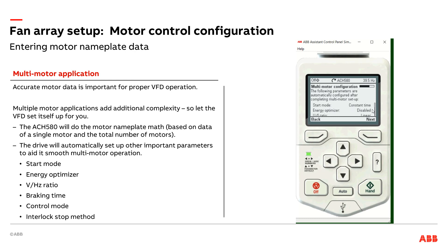Energy optimizer has been disabled. One of the neat things with the drive is it can vary the voltage based on frequency — normally that's how it controls speed — but it can also adjust that voltage at a specific frequency to find the sweet spot for energy efficiency. That works well with a single motor application. With a multi-motor application it just doesn't work as well because you increase the chance of getting a bad spot where you might stall out. So by default we disable the energy optimizer functionality to avoid problems in a multiple motor configuration.